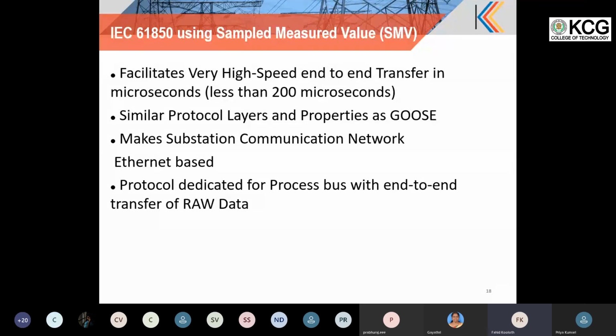control block. So this is high speed transfer of sampled values from all the process devices, with continuous transfer, whether the value is changing or not changing is immaterial, and the recommended timeline is 200 microseconds. It is completely transmitted from the process level equipment to the bay level equipment. The bay level equipment takes this, processes it and uses it for protection and other functionality, then sends protection and other signals out to the station level using MMS, and if this needs to be informed to other IEDs, it can be sent out using the GOOSE mechanism.